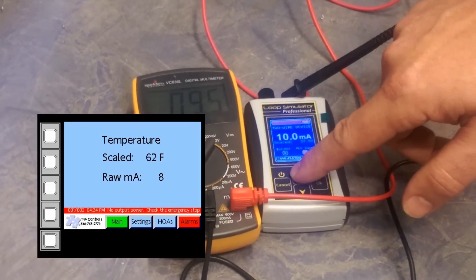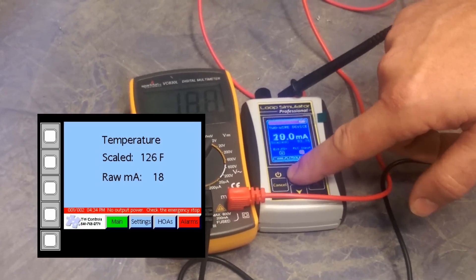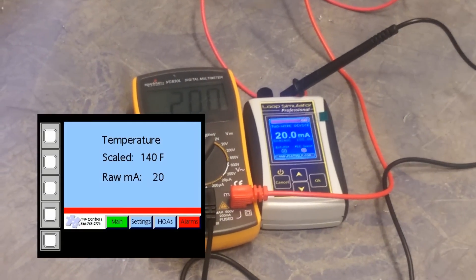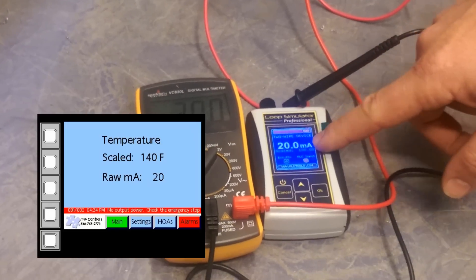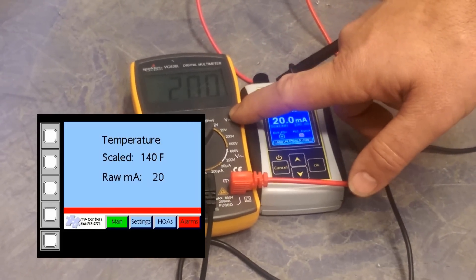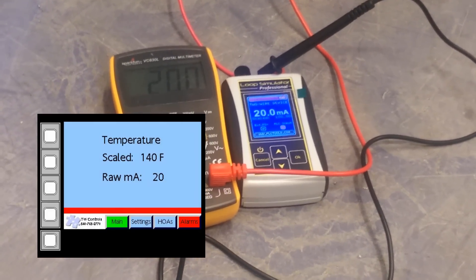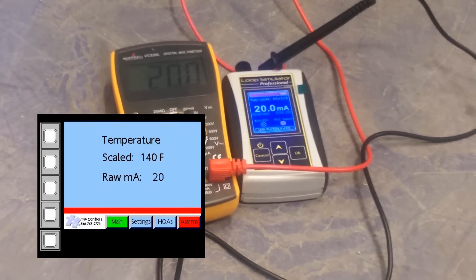And I'm not going to go through each one of them. As you can see, as we bump it up, it bumps up on our meter until we get to 20 milliamps. Now our simulator shows that we're putting out 20 milliamp. Our meter shows we're putting out 20 milliamp. Our HMI shows 20 milliamp. And our scale value shows 140 degrees Fahrenheit.